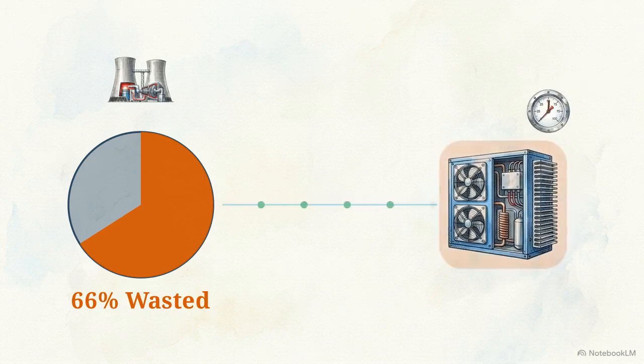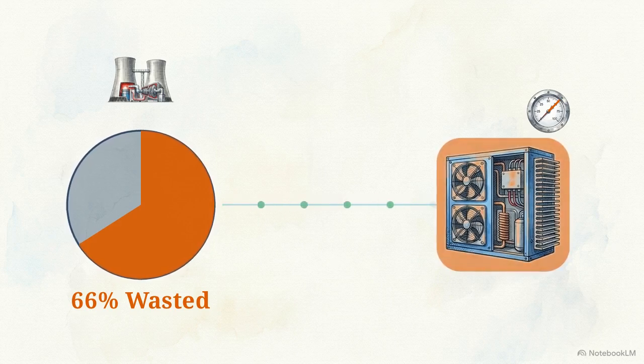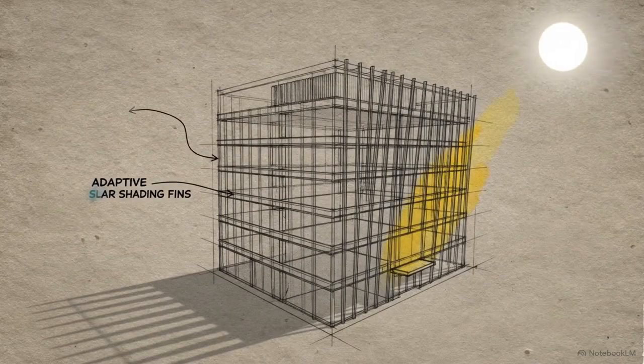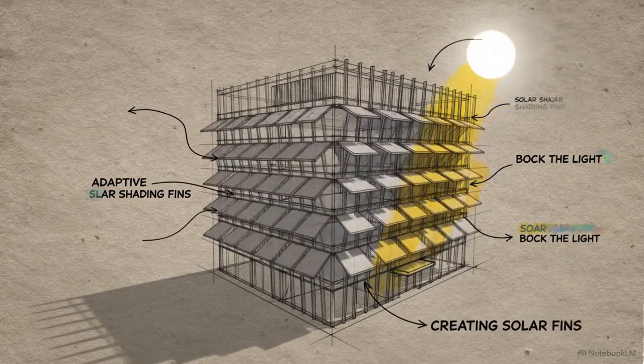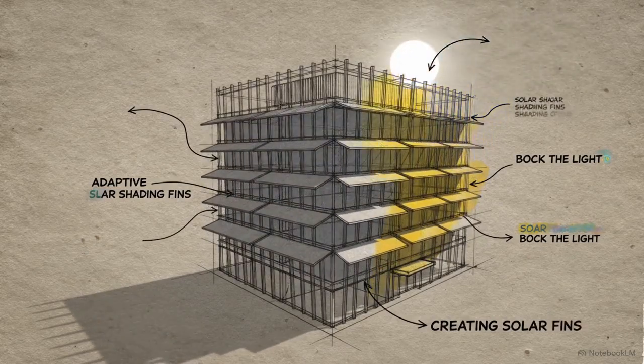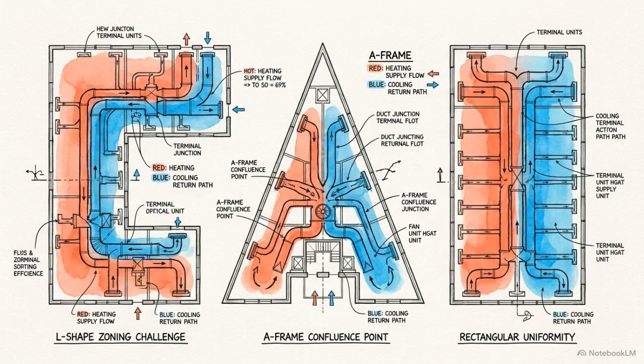If a building runs an oversized chiller or a poorly selected boiler, that mechanical inefficiency forces a massive overconsumption of raw global resources upstream. To mitigate this grid inefficiency, engineers build inherent thermal control directly into the architecture of the structure itself. The physical shape of a building, whether it is L-shaped, A-shaped, or rectangular, dictates where heavy equipment can be located and how ductwork and piping are routed.